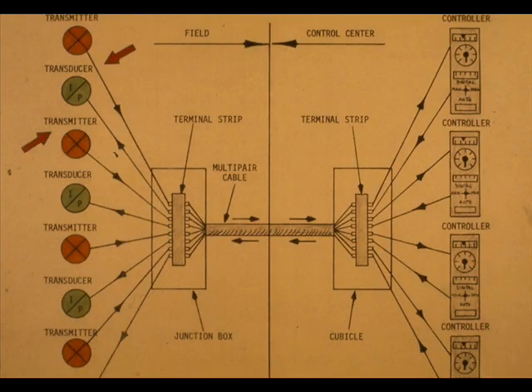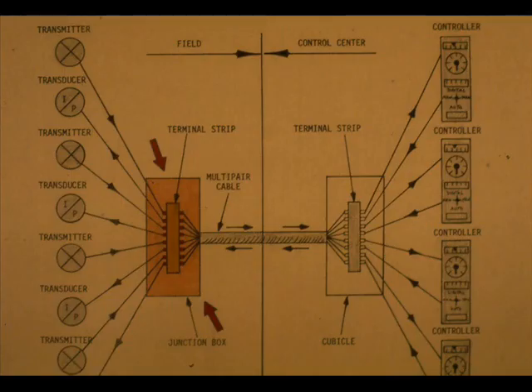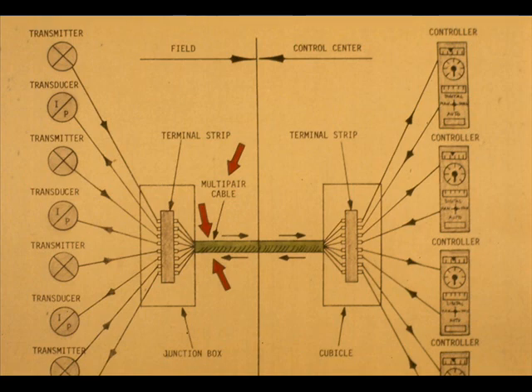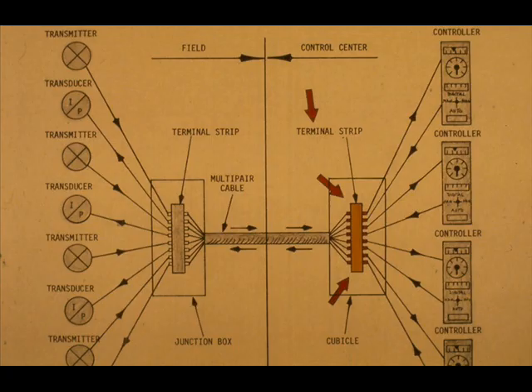This schematic represents the circuits previously described. The field items are transmitters, transducers, and the junction box. The signal wires are connected to a multi-pair cable through a terminal strip in the field junction box. The multi-pair cable terminates at a terminal strip that is located inside a control center cubicle.